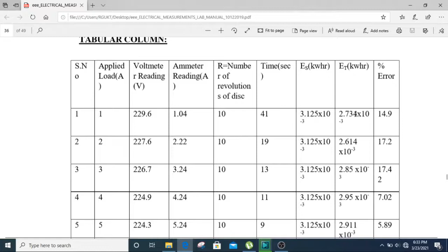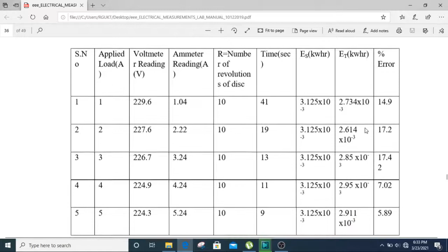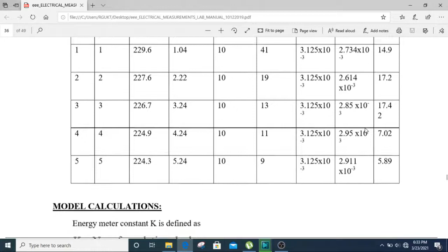Likewise you apply loads from 1 amp to 5 amps, then you can find the true energies for different loads, and you compare all the true energies with the measured values. You compare these two values by finding the percentage error. Measured value minus true value, by true value, into 100, gives the percentage error. Likewise, for different loads you find the percentage error.